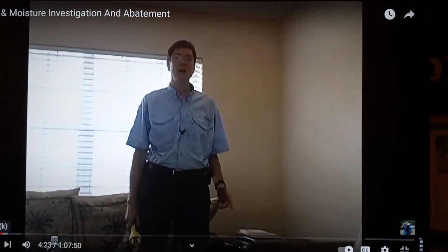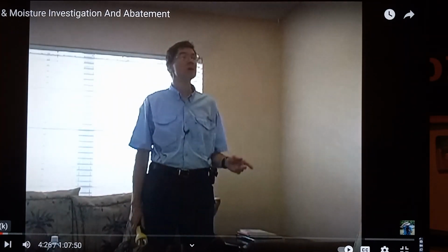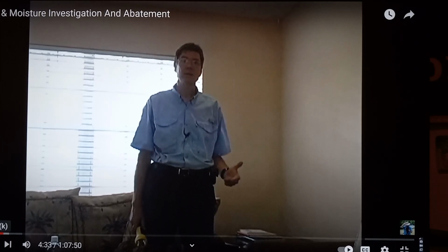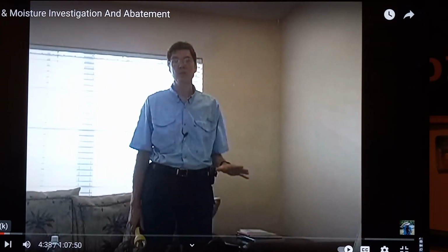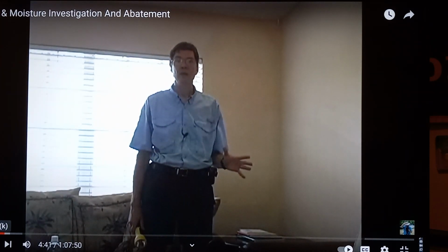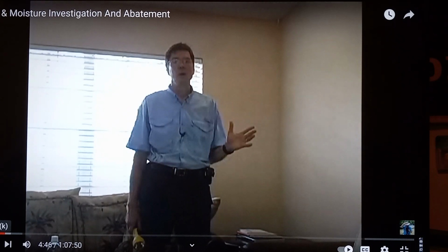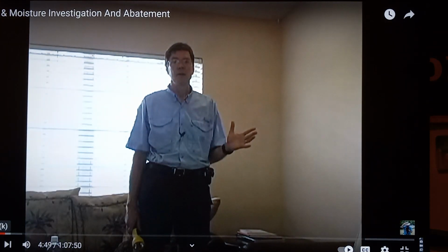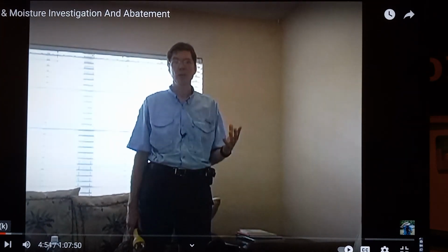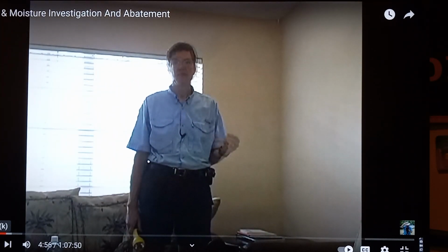One of the problems in hot, humid climates is condensation, especially around HVAC supply vents. If this isn't corrected and humidity levels aren't dropped, then it creates a favorable condition for mold to grow on the vent as well as around the vent on the surrounding drywall or materials. Mold growth on a metal vent is not on the metal itself, but on the dust and debris that accumulates on the metal. The vent should be kept dry and clean.